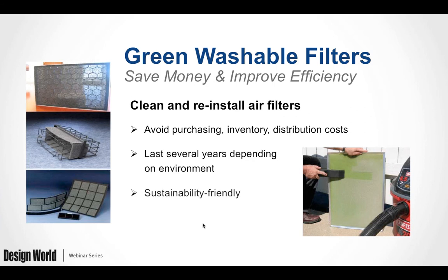This power cabinet example shows the exhaust side of the cooling fan pictured at the right side, and on the left side is the super clean inside of the electrical cabinet as a result of using a properly specified air filter to keep equipment running at optimum efficiency. Washing filters is easy and most times you can clean without the need for water — just use a vacuum or blow out with compressed air to clean and reuse. This saves on purchasing, logistics, and storage, as the filter should last at least a few years if the environment the equipment is deployed in is not overly corrosive.